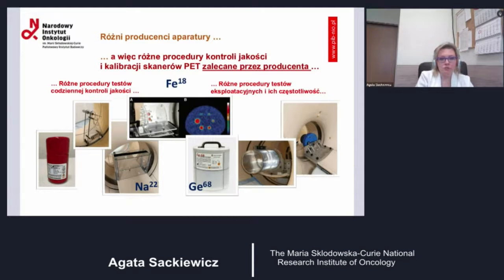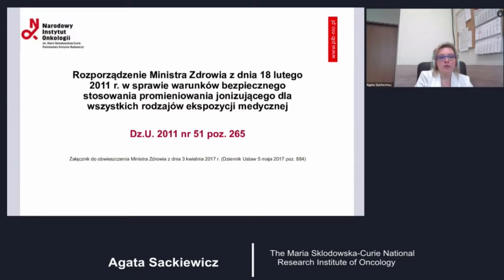When we are talking about the CT part of the equipment used in Poland, there is a standard that is maintained in accordance with the standard for computer tomography. All the devices, all the apparatus will be covered by various tests and controls involving the use of fluorine-18, so the basic isotope we are working with. So there is quite a diversity of aspects we have to address when we are conducting tests. We also have to comply with the regulation that lays down the obligation of conducting the tests.